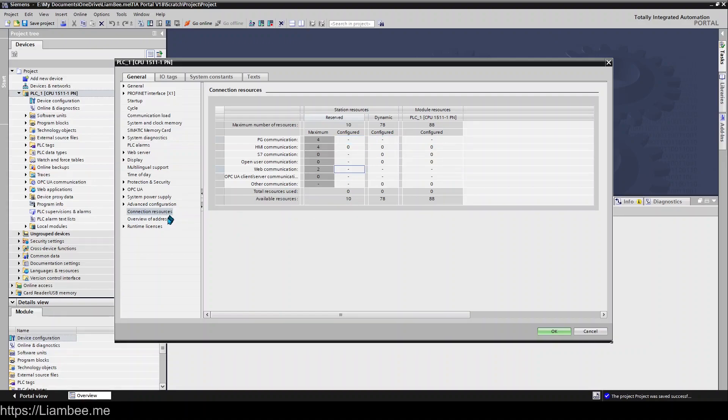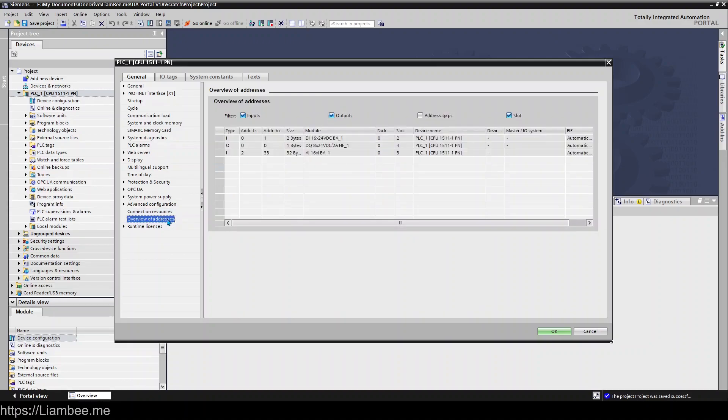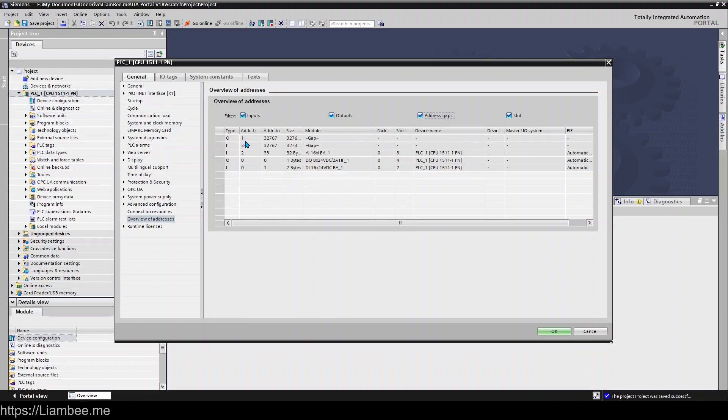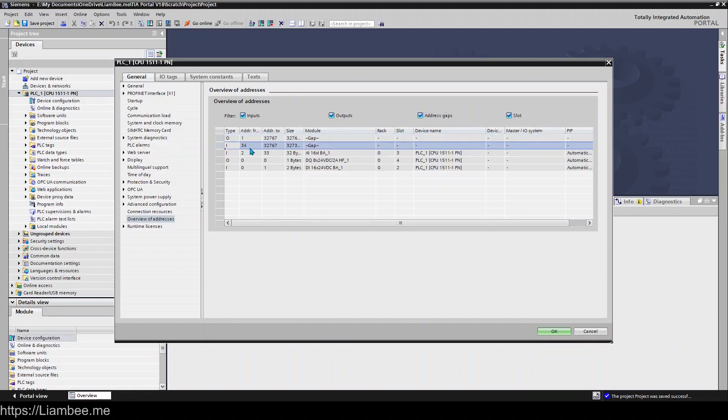And then you have an overview of addresses which is a very interesting place to come and have a look when you've finished setting up your hardware layer because this tells you whether you've got any gaps in your addressing. And so you can click here and go to address gaps and we can see that between our outputs one to 32,767 that's a gap and the same on our inputs but from 34 to 32,767 that's a gap. So it's useful to find out where you have spares if you're going to add new modules and things like that rather than TIA portal keep coming up saying that's wrong something else is already on this.